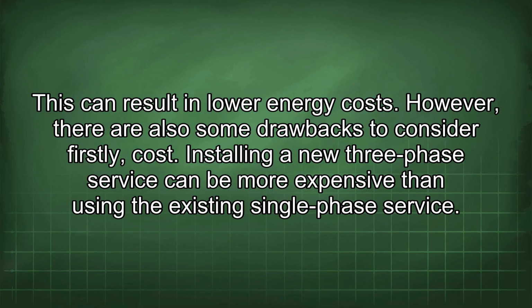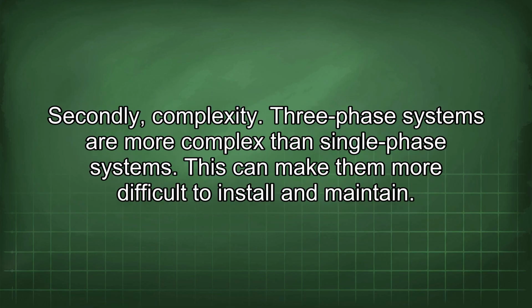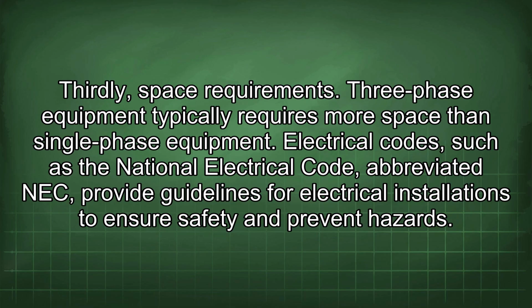However, there are also some drawbacks to consider. Firstly, cost. Installing a new three-phase service can be more expensive than using the existing single-phase service. Secondly, complexity. Three-phase systems are more complex than single-phase systems. This can make them more difficult to install and maintain. Thirdly, space requirements. Three-phase equipment typically requires more space than single-phase equipment.